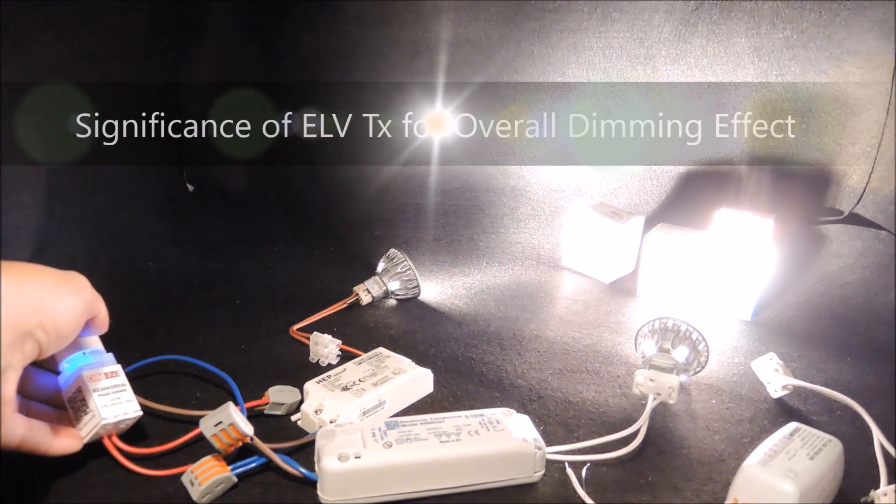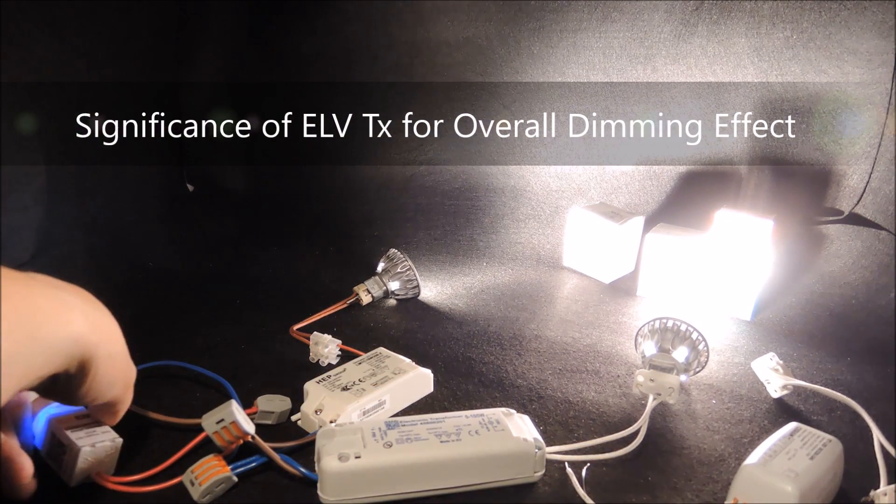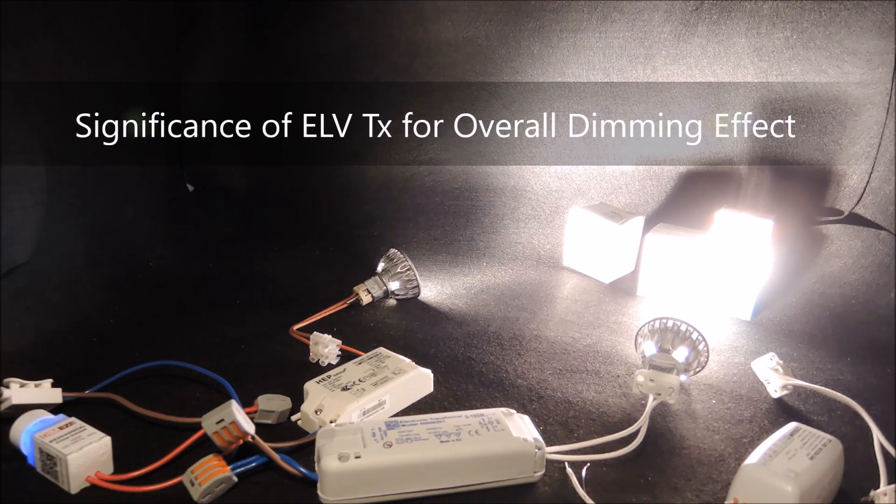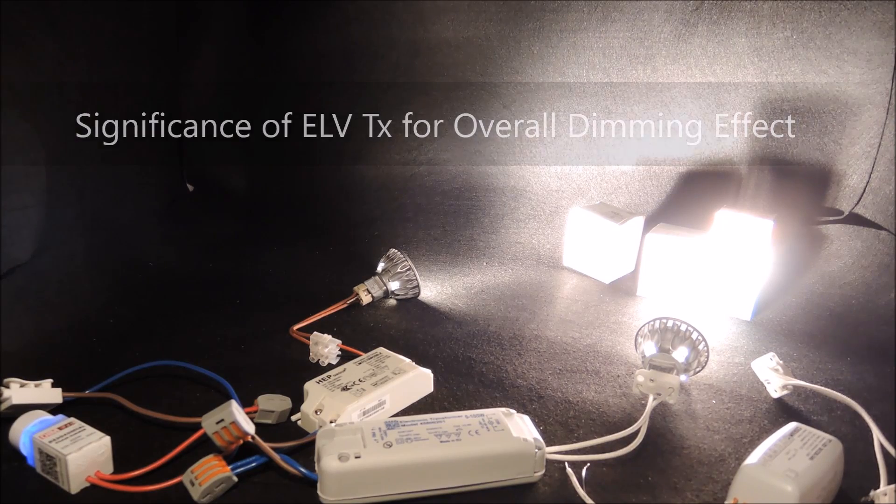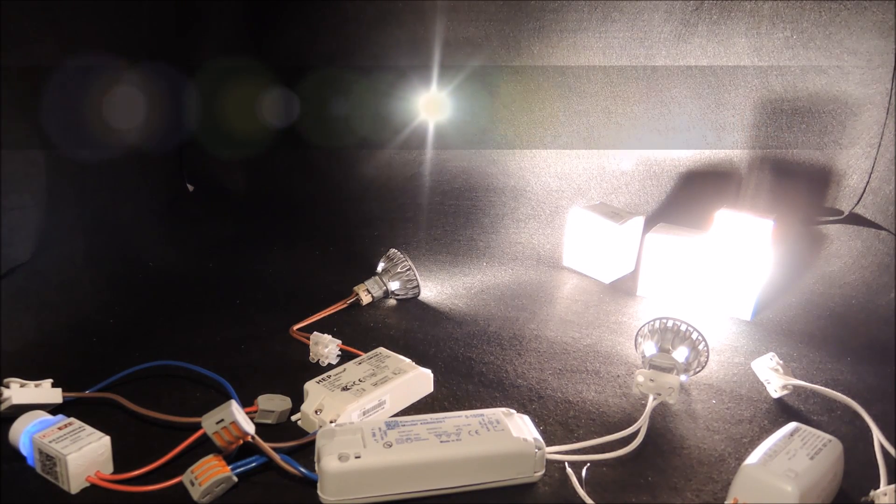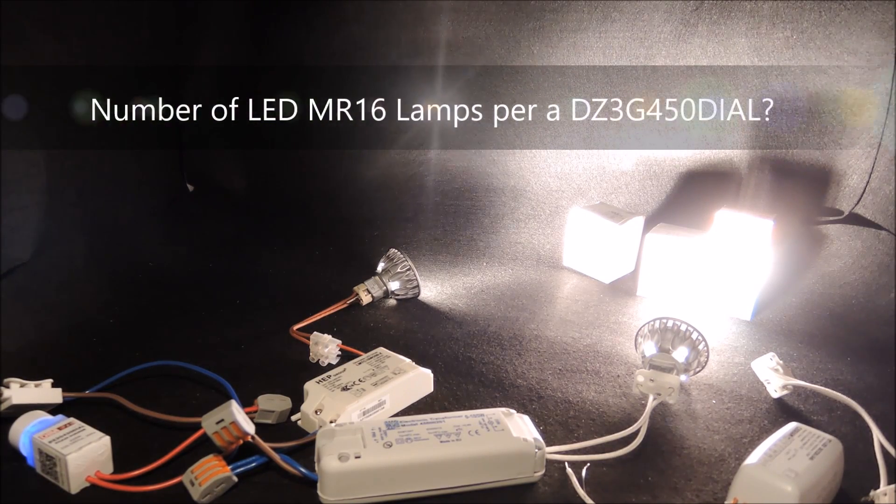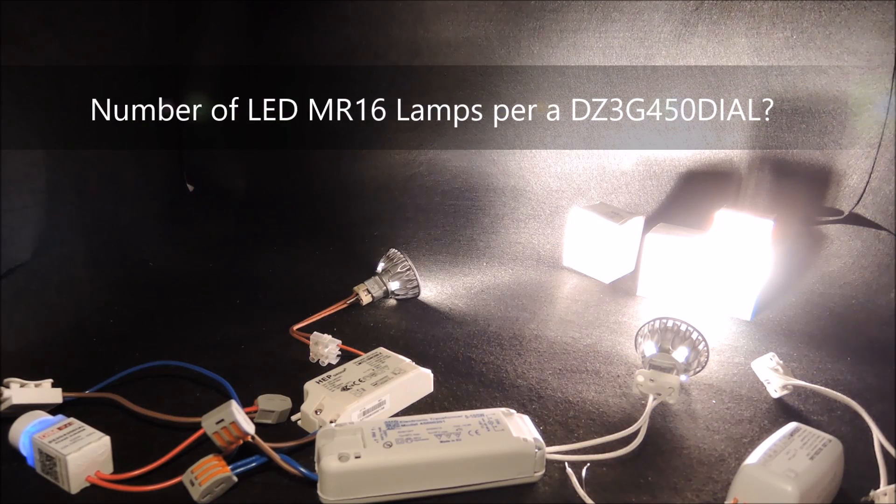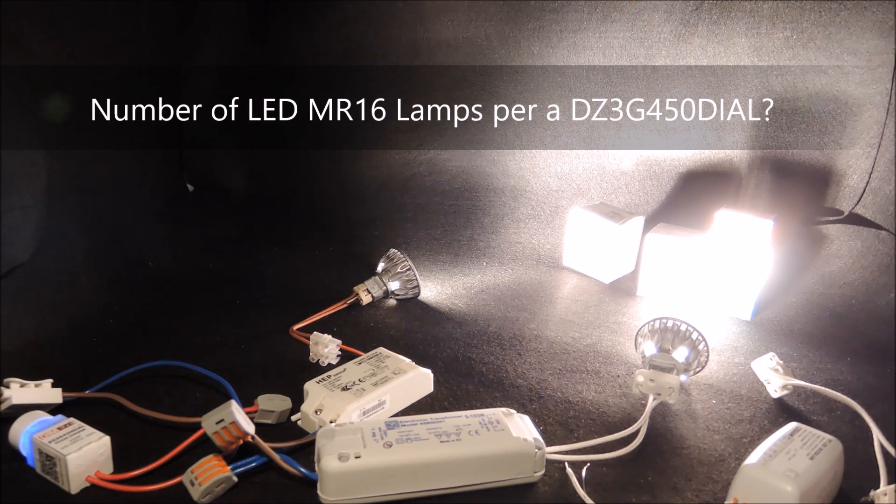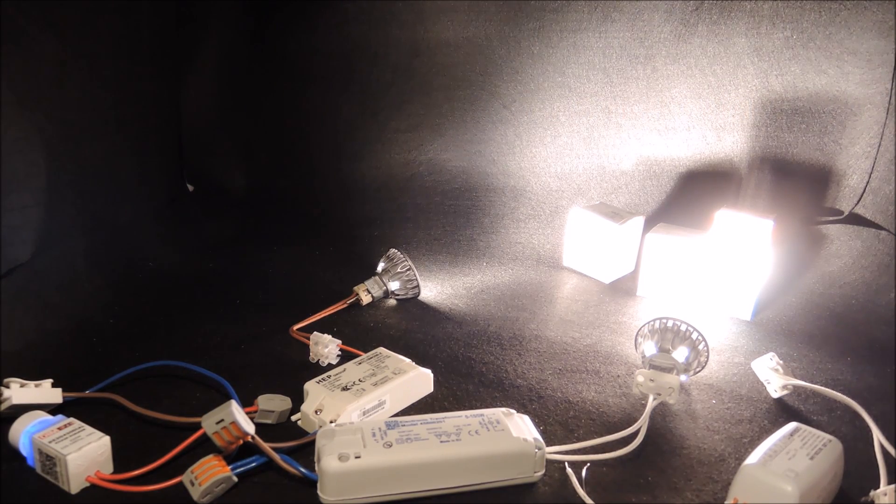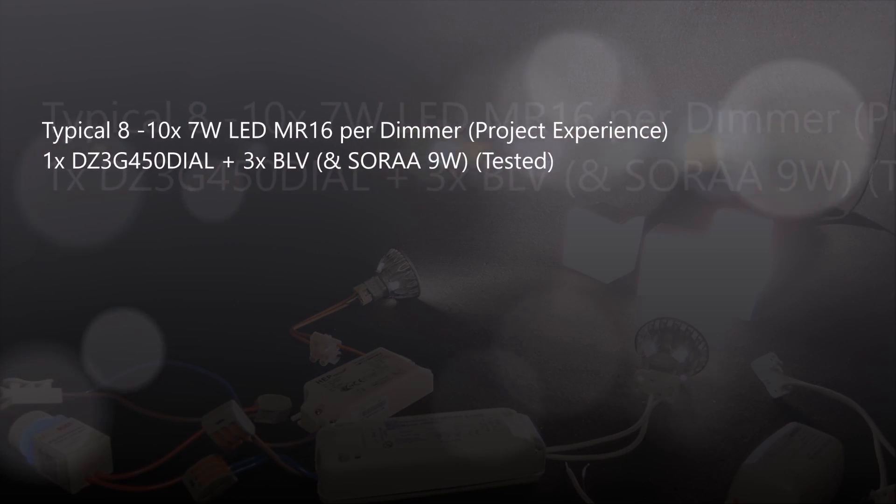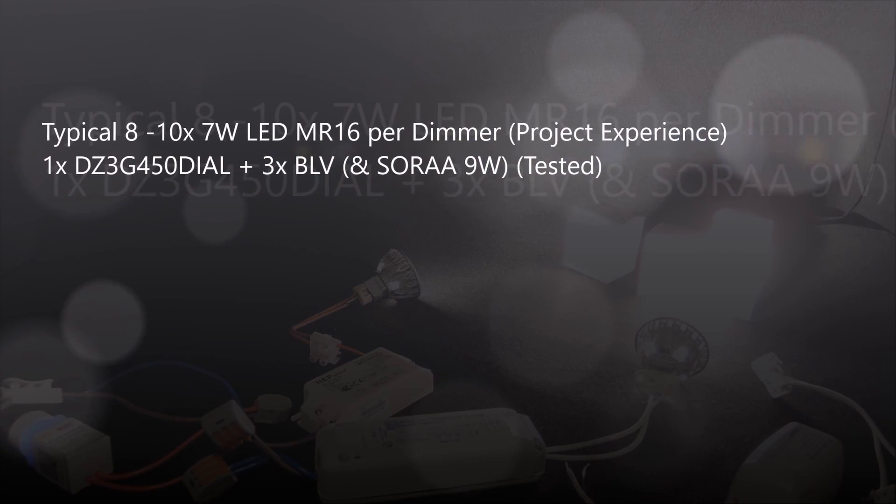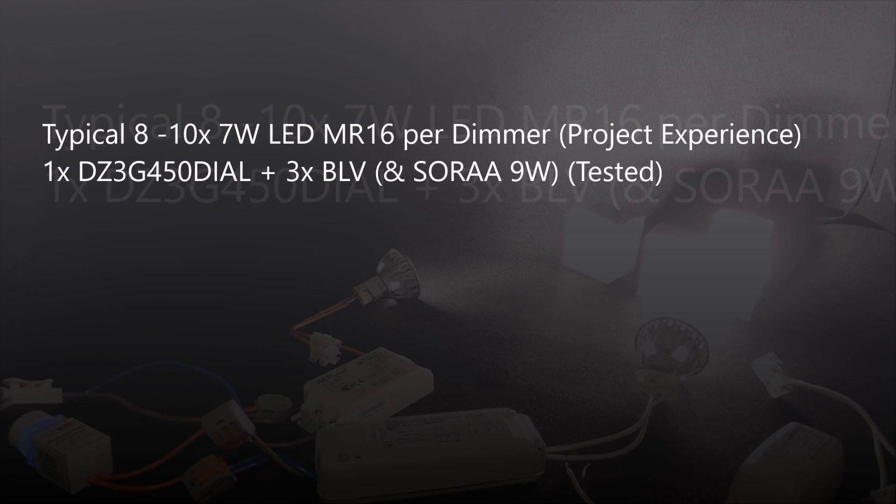This definitely shows the significance of electronic transformers to the overall dimming effect. Now, the next common question is how many number of lamps can be connected to a single dimmer? Without getting into the inrush current calculation details, we will suggest a typical of 8-10 of 7W LED MR16 lamps per dimmer based on actual project experience.